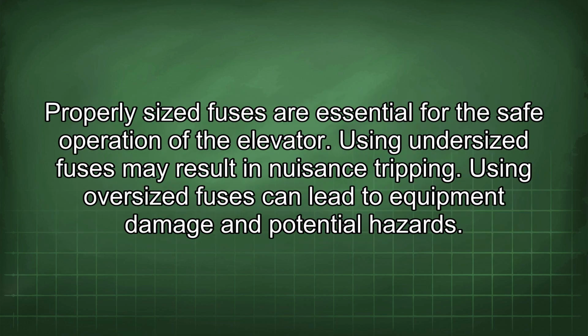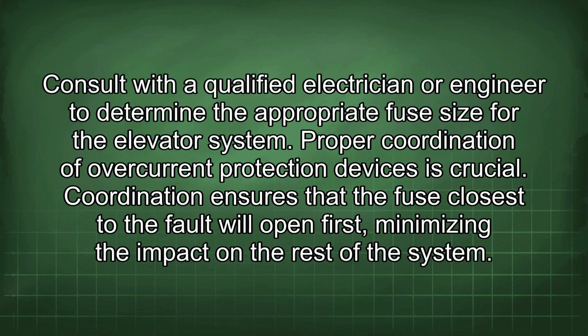Properly sized fuses are essential for the safe operation of the elevator. Using undersized fuses may result in nuisance tripping. Using oversized fuses can lead to equipment damage and potential hazards. Consult with a qualified electrician or engineer to determine the appropriate fuse size for the elevator system. Proper coordination of overcurrent protection devices is crucial. Coordination ensures that the fuse closest to the fault will open first, minimizing the impact on the rest of the system.